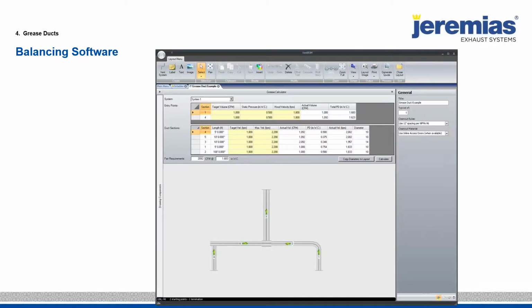Also want to point out that we get a lot into balancing. So if you have multiple hoods, let's say that you needed 1,000 CFM at both of these locations, this duct actually shows 100 feet here and only 10 feet on this side. And by using different style of fittings, we can actually balance out the hood systems.